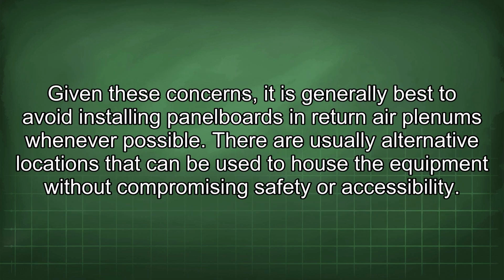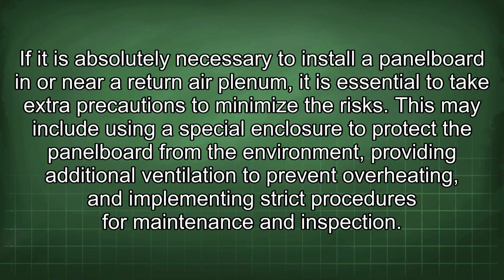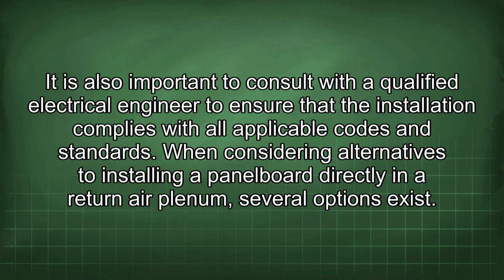Given these concerns, it is generally best to avoid installing panelboards in return air plenums whenever possible. There are usually alternative locations that can be used to house the equipment without compromising safety or accessibility. If it is absolutely necessary to install a panelboard in or near a return air plenum, it is essential to take extra precautions to minimize the risks. This may include using a special enclosure to protect the panelboard from the environment, providing additional ventilation to prevent overheating, and implementing strict procedures for maintenance and inspection.